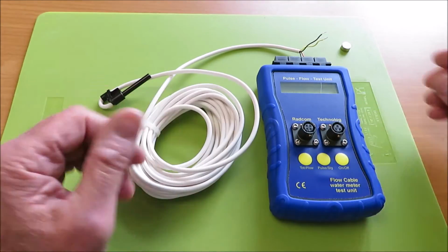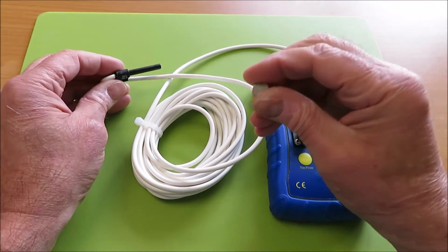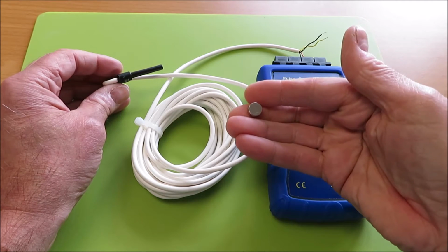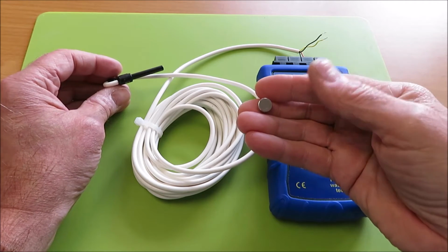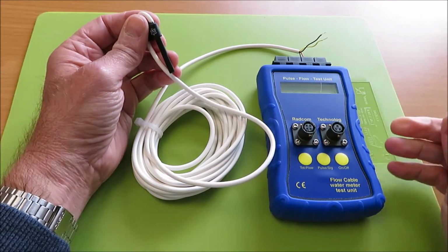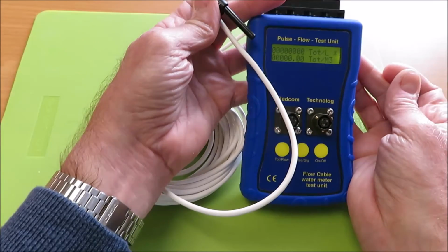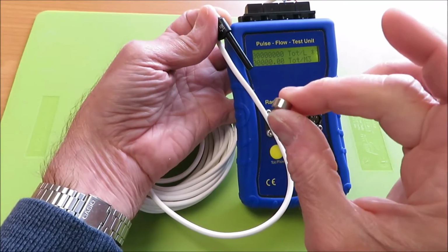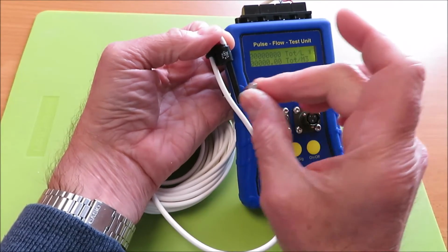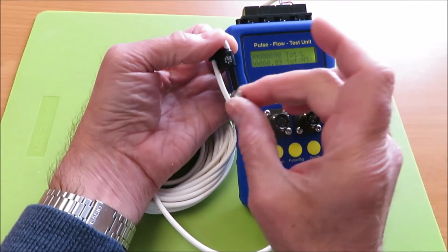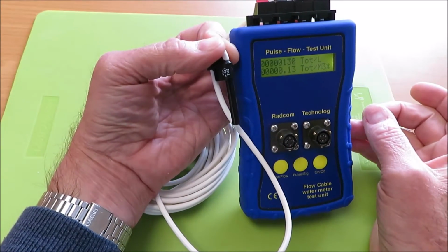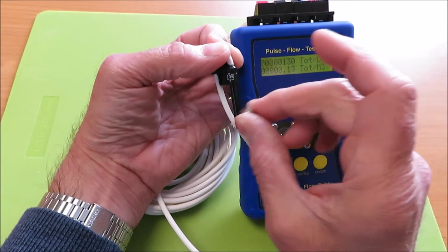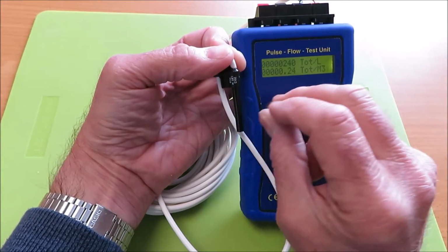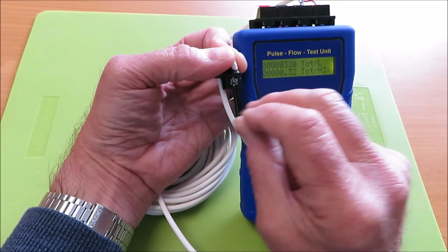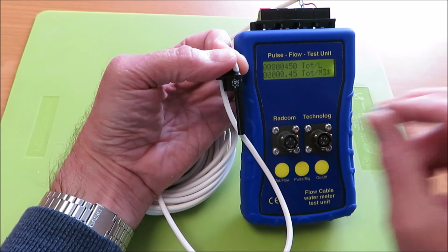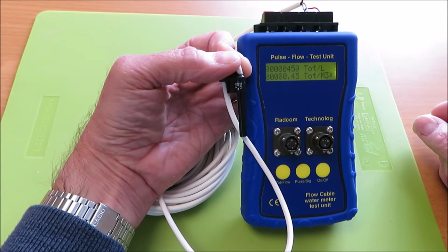Now, what I would use to test the unit is just a basic magnet. That's a neodymium. It's a very strong magnet. And basically all you do to test it is, if I can get the display so you can see it, you'll actually pass the magnet across the sensor at this point. And what you should see is that you get a reading of pulses as they go. I don't know whether you can see the asterisk on the right hand side moving up and down as I pass each one of those. So that actually confirms that the unit is working.